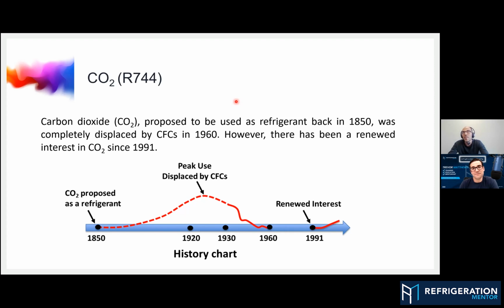And this is also another thing where CO2 could be an advantage, because distribution of liquid CO2, for example, to different boreholes could be less challenging compared to other refrigerants. So these are all benefits or advantages of using CO2 for a direct expansion system. But honestly, in the last 10 years I've been doing research, I still believe a direct expansion system is a very good system for residential application or light commercial application, not for big projects where you need 200 or 300 boreholes. When it comes to, let's say, 5 boreholes or less, this direct expansion is probably going to be the best system. But this is my opinion on that.